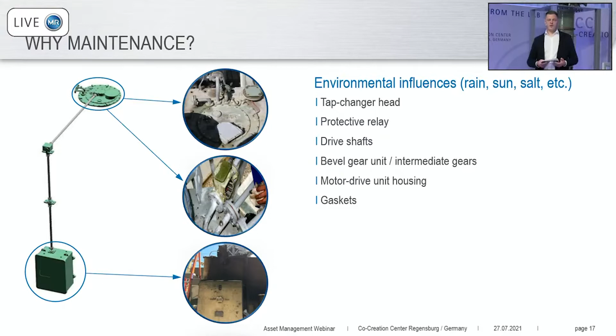One very important point is that MR is not just developing our new products, we are also developing the products which we have in our current product portfolio. So for example, on the top, we have the contact leads. In the past, they had a maintenance interval of 150,000 switching operations. MR developed them further, and now we can give this benefit to you. So the contact leads must now be changed between 300 and 400,000 switching operations, which is very good. And below, flexible leads. This is a contact shell of an OILTAP M. Left is the former design, and on the right side you see the flexible lead, after the maintenance. So we are also upgrading them.